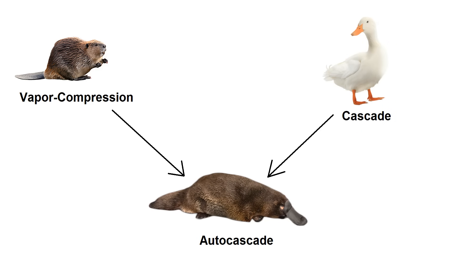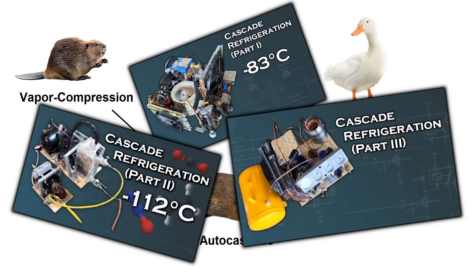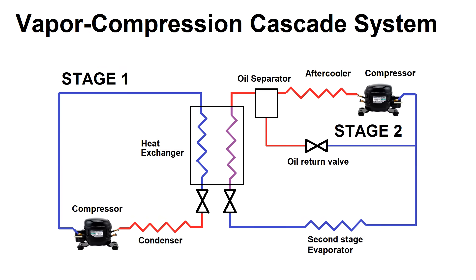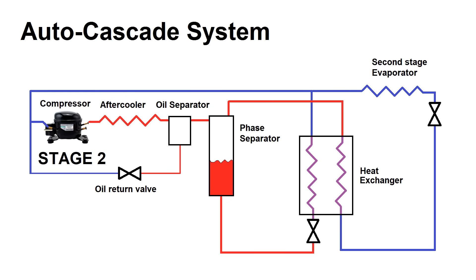In earlier videos, I explained the inner workings of a typical vapor compression cascade cycle, which uses two refrigeration loops with two different compressors for two different refrigerants so that you basically have one refrigerator cooling a second refrigerator so that it can get even colder. The autocascade system also uses multiple refrigerant loops, but just one compressor.